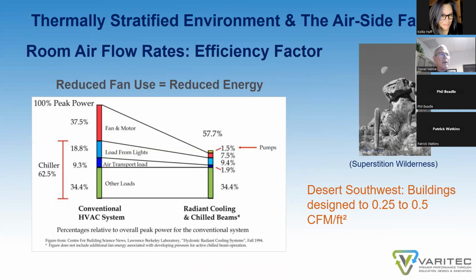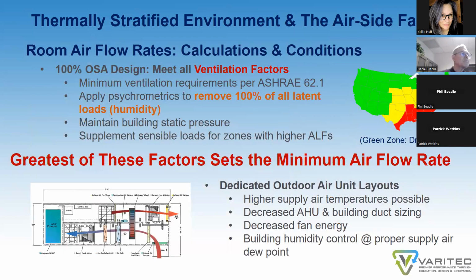And by reducing the amount of air supplied to a building, allowing heat transfer to take place on the chilled water loop, you can reduce fan energy significantly. And it's not uncommon to see 35 to 40% reduction of energy due to a reduction of horsepower necessary to move energy to and from a building.